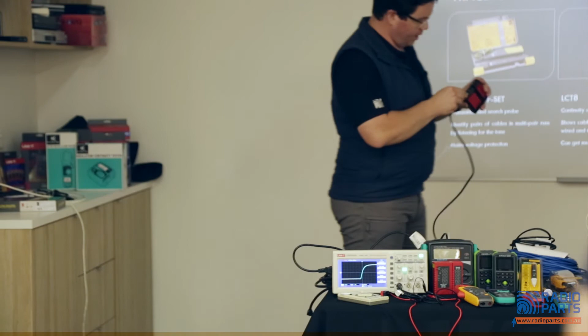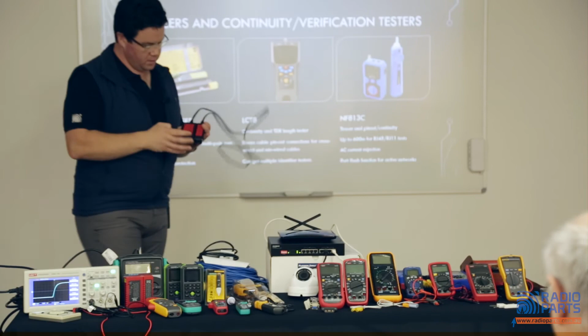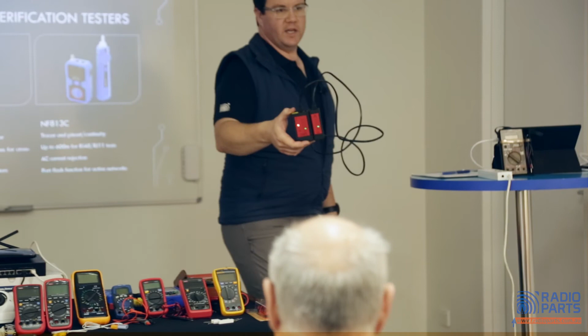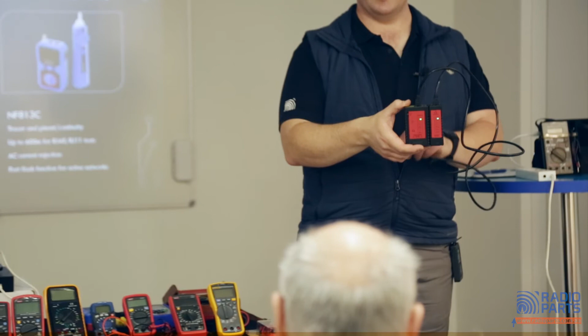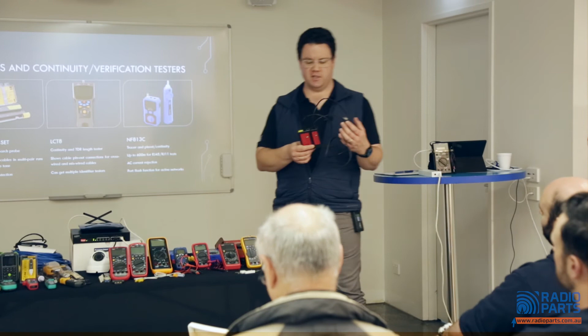So I take a good cable, plug it in, and put it into test mode. You can see the little LEDs run down—number 1, number 2, number 3, number 4, number 5, number 6, and so on. My shields are all connected, and hey look, copper is connected to copper. Great. That doesn't tell me how good that cable is, it just tells me copper is connected to copper.